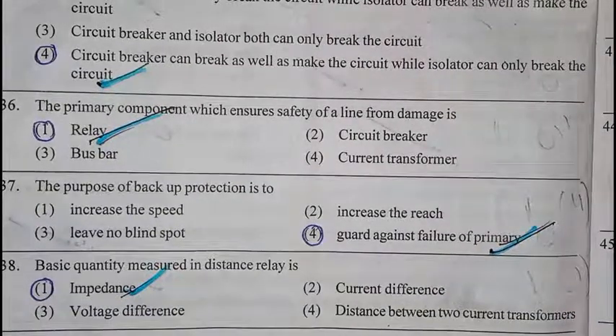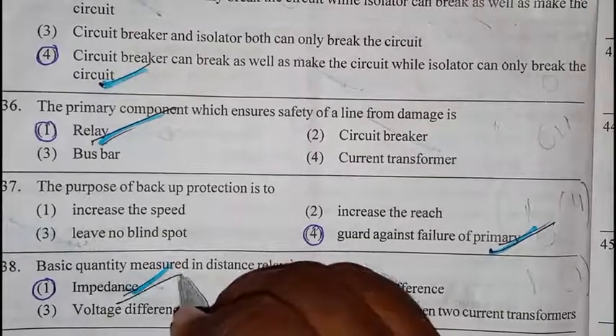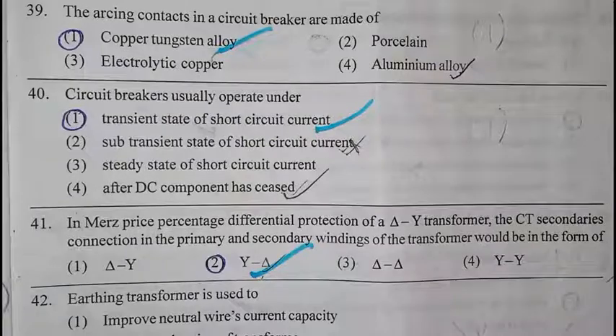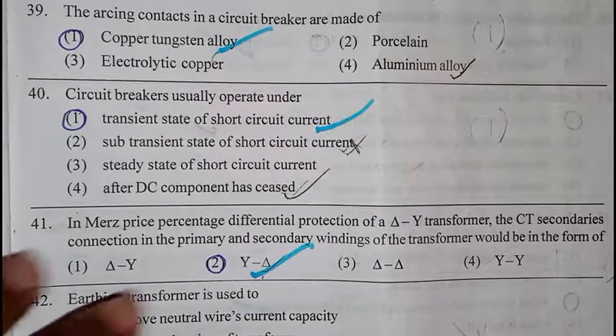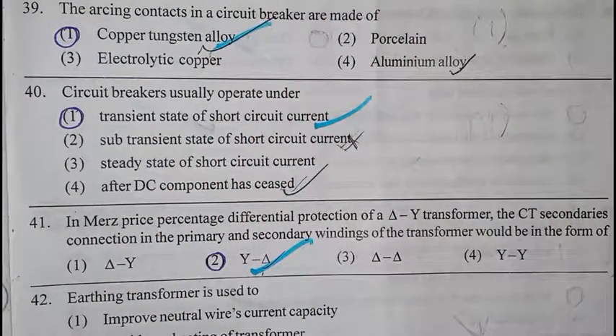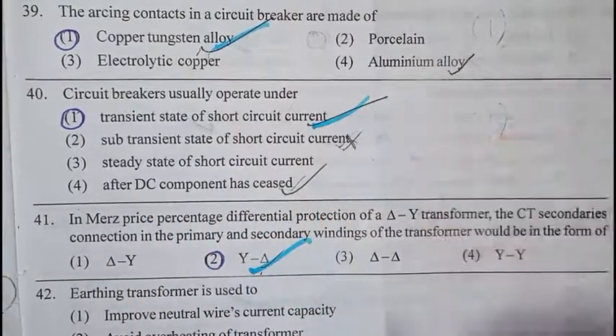Question number 38. Basic quantity measured in distance relay is. Answer: impedance. Question number 39. The arcing contacts in a circuit breaker are made of copper tungsten alloy. Question number 40. Circuit breaker usually operates under transient state of short circuit current.